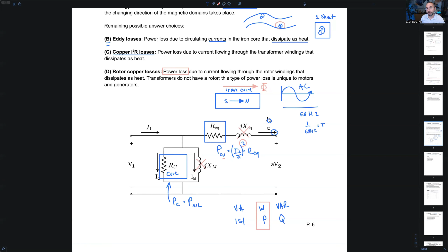Arthur asked, what would those reactance losses be called? There are no power losses - reactive power travels back and forth from the power supply to the load, just changing. Think of two water balloons filled with water, just moving it back and forth - there's no actual water lost. Whereas your real power losses in watts are like a slow pinhole leak, where real power is dissipated as heat to the atmosphere - you lose it from the system.